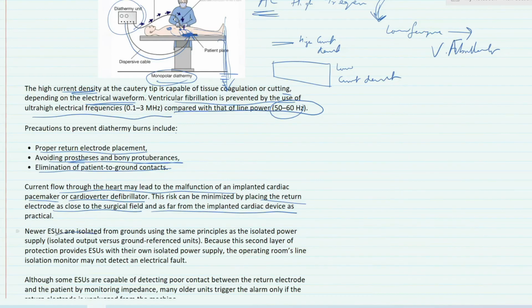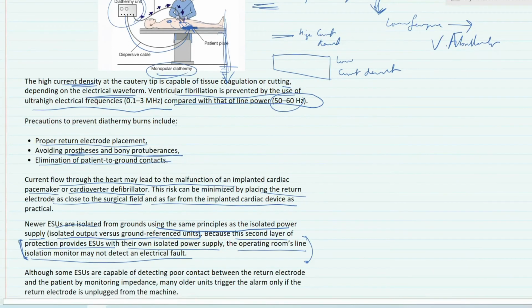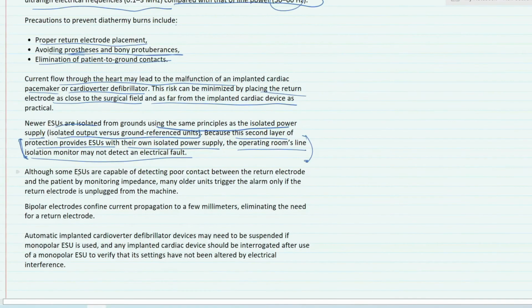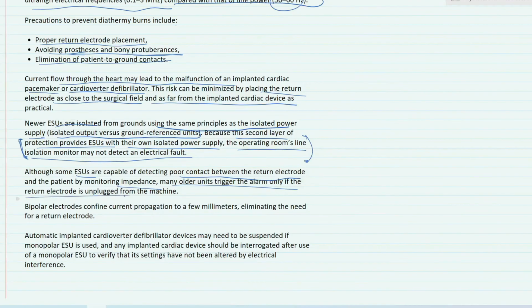Now, newer ESUs are isolated from grounds using the same principle as the isolated power supply that we have already discussed: isolated output versus ground reference units. Because this second layer of protection provides ESUs with their own isolated power supply, the operating room's line isolation monitor may not detect an electrical fault. Now this is important right here. So this is also one of the loopholes of line monitors that can cause hazards. Now, although some ESUs are capable of detecting poor contact between the return electrode and the patient by monitoring impedance, many older units trigger the alarm only if the return electrode is unplugged from the machine.